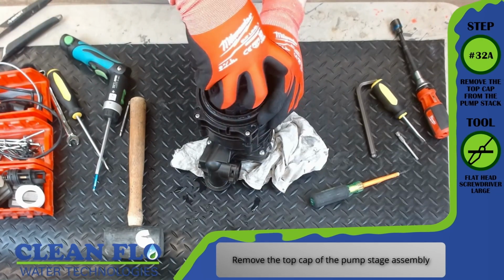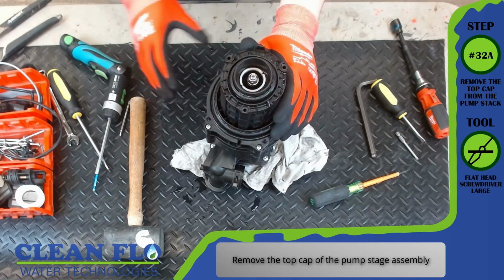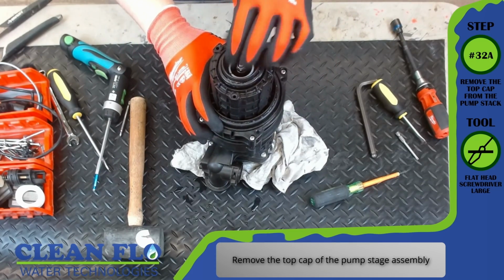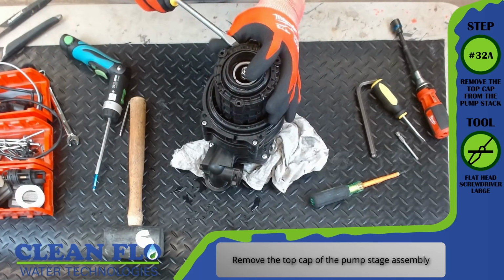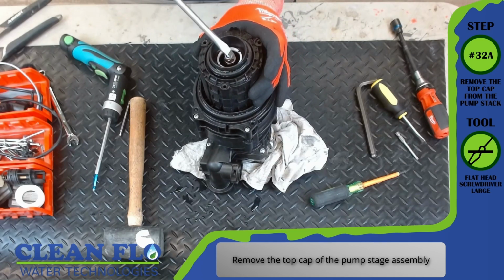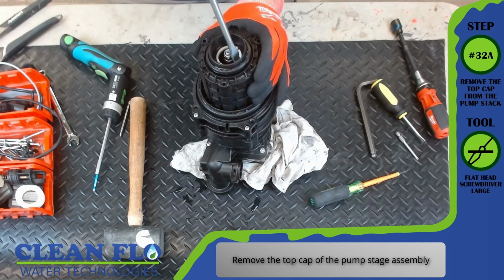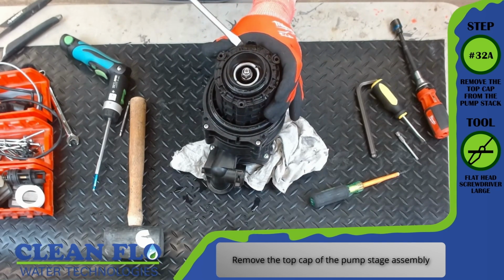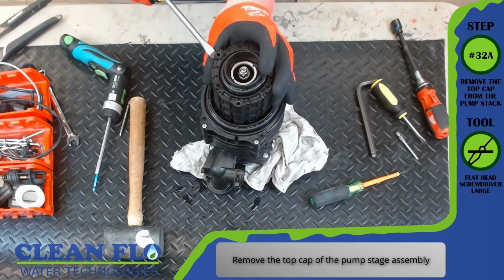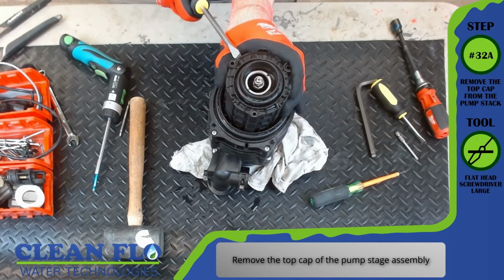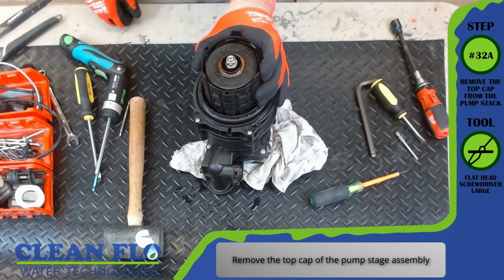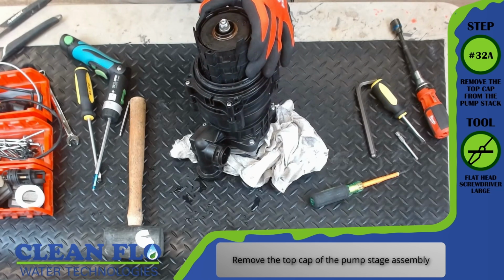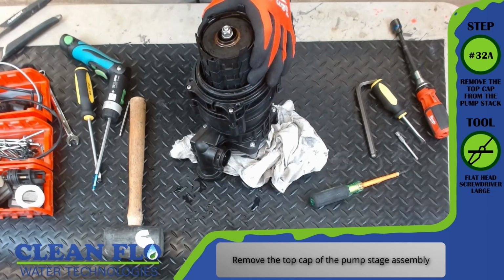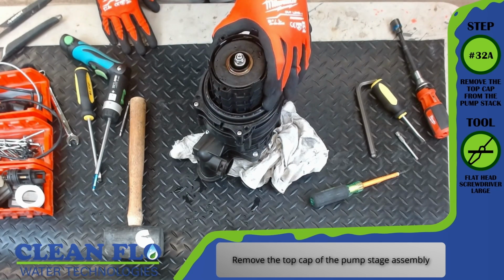Step number 32A, remove the top cap from the pump impeller stack. Tool, large flathead screwdriver. Remove the top cap from the pump stage assembly. When using the flathead screwdriver, be sure to use minimal force and to not deform the plastic. Finding the right location to properly pry from is crucial.